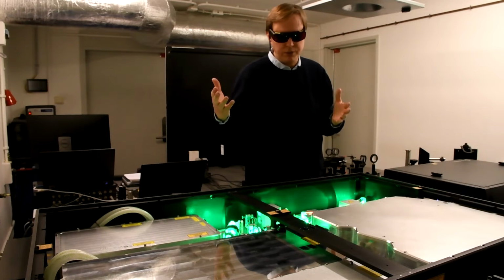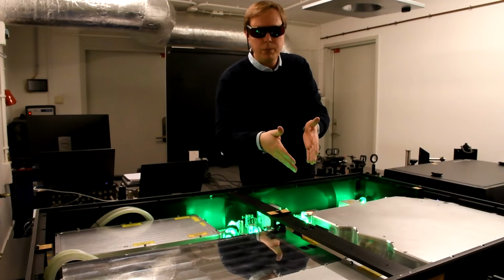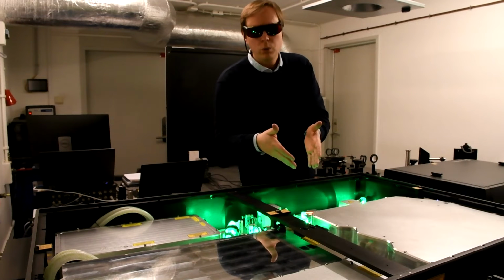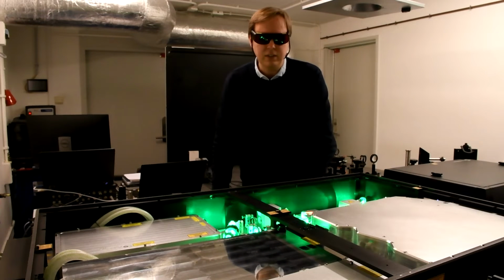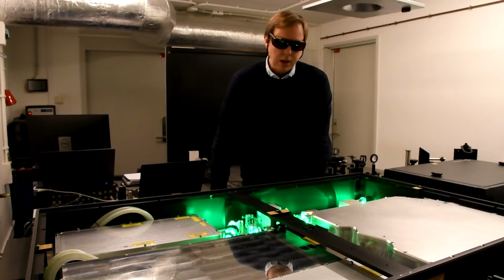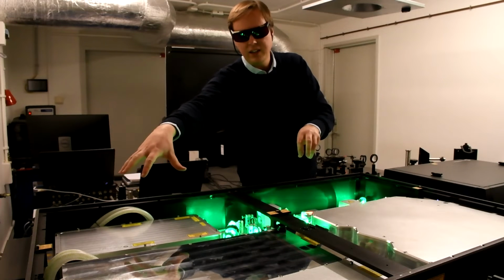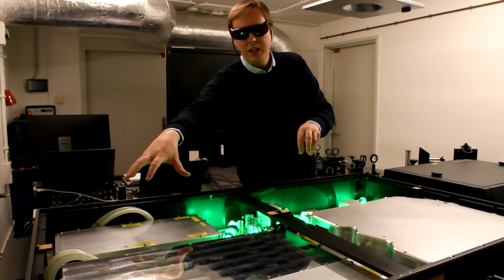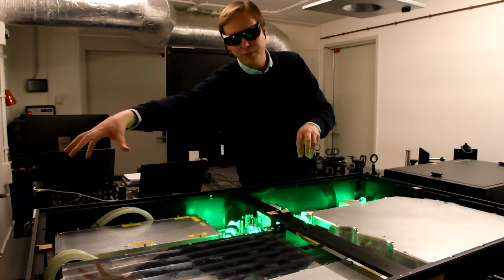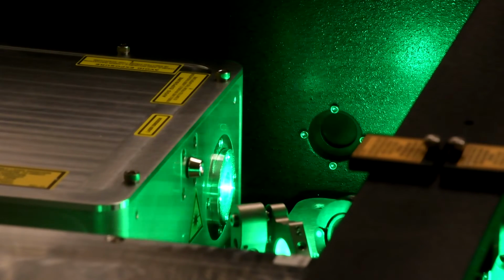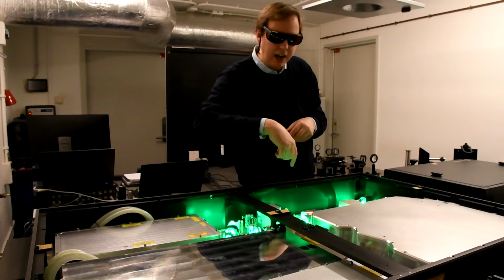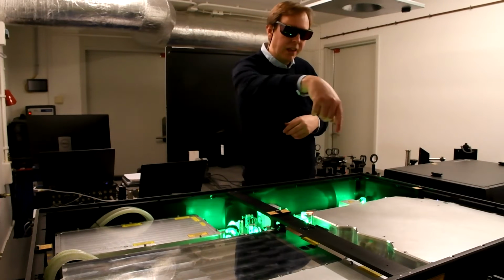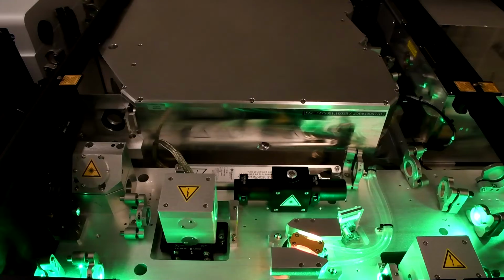So that consists of an additional gain medium, which is the same crystal, which supports this broad band of all the wavelengths. It's called titanium sapphire crystal. And that is pumped with a laser here, and that is the green laser. And the green laser consists of another laser first. It's a 1064 that gets frequency doubled to 532. That's visible, that's why you experience now it's green. And that is coming in here, pumping this gain medium, and then you're sending in this femtosecond pulse.